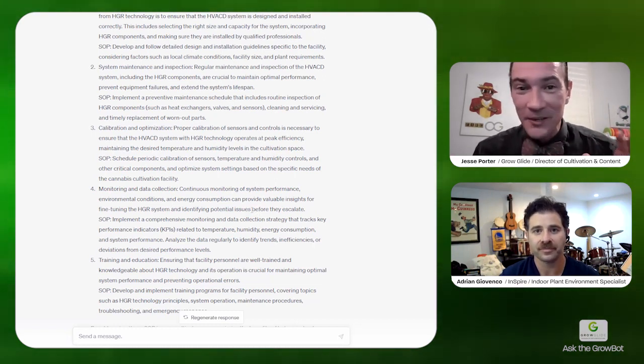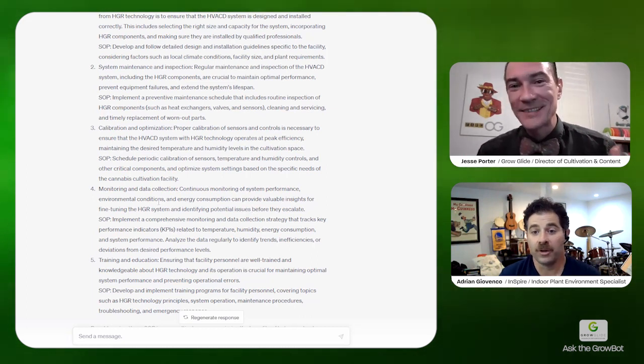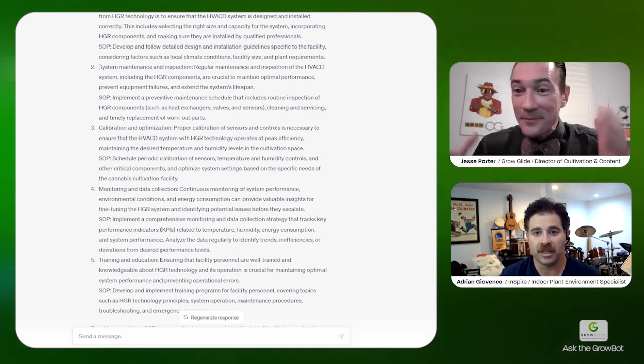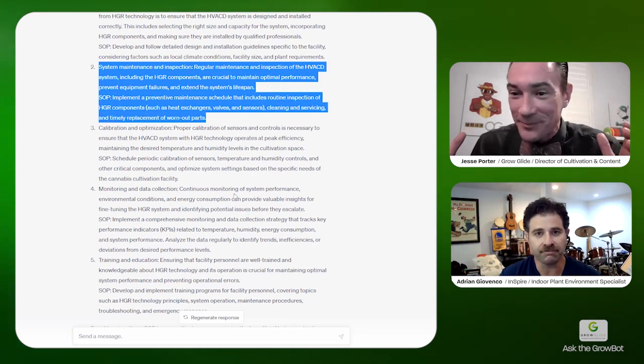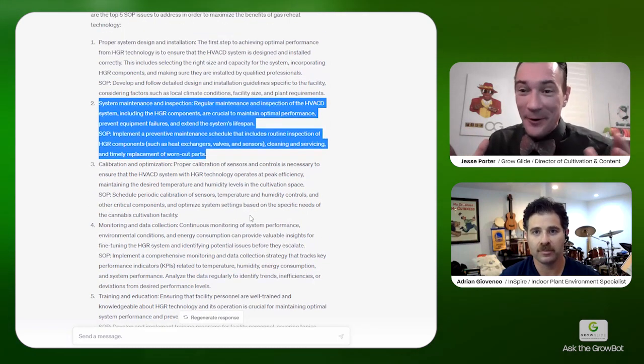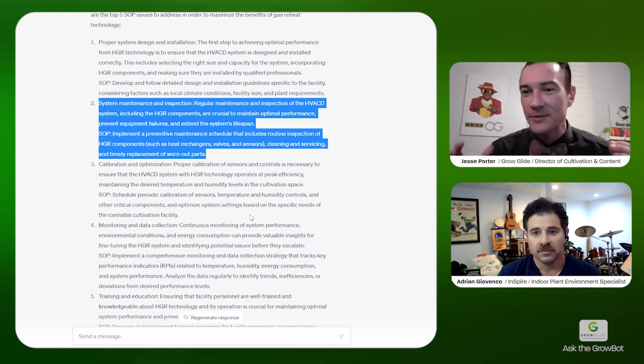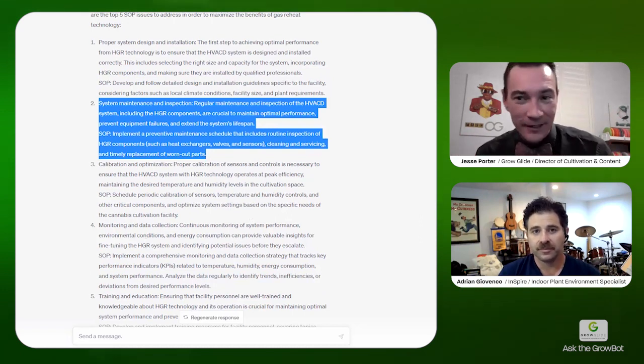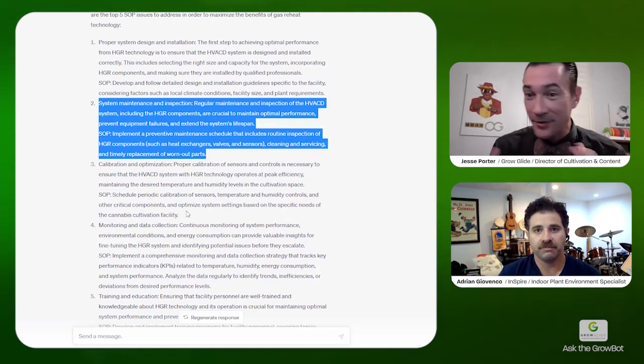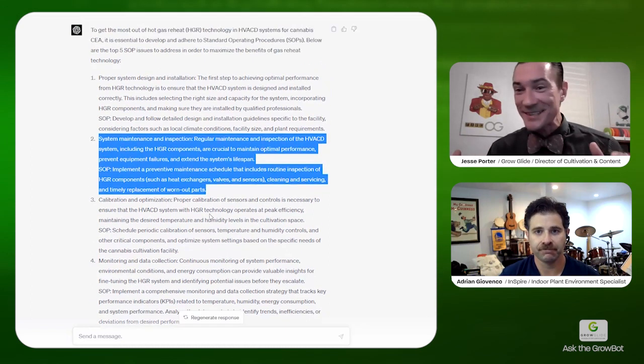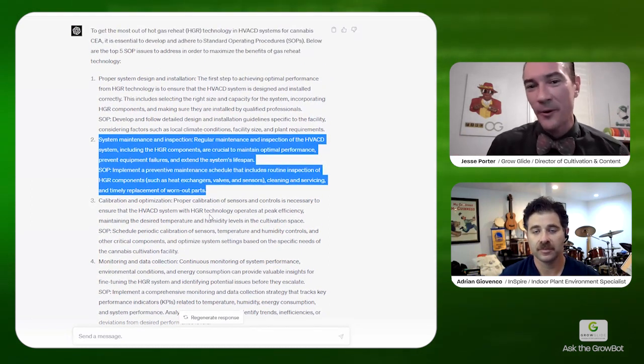You lacked commissioning altogether, like number 2 points to here: system maintenance and inspection. Maybe your ductwork has a bunch of holes in it, I don't want to call anybody out, but you know what I'm talking about. You're not able to effectively deliver the CFMs that you thought you had, and you'll never be successful until you solve for that pinch point.